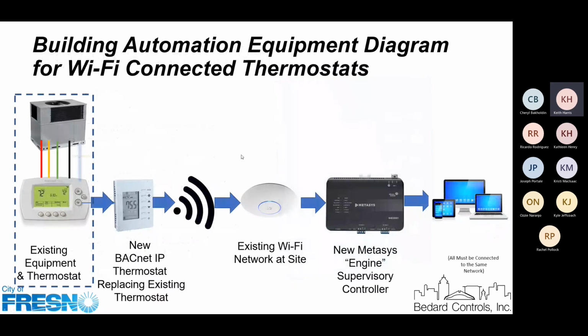So this is kind of how it works. We replace the existing thermostat with the BACnet IP thermostat. We then connect it to the existing Wi-Fi network at the site. That Wi-Fi network then talks to what we refer to as a Metasys engine or supervisory controller. And then that supervisory controller talks to a server that allows people to remotely access the data through credentialed login.